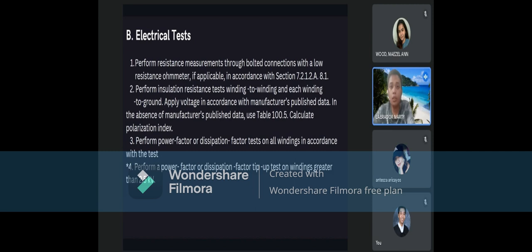2. Perform insulation resistance test winding to winding and each winding to ground. Apply voltage in accordance with manufacturer's published data. In the absence of manufacturer's published data, use table 100.5. Calculate the polarization index.